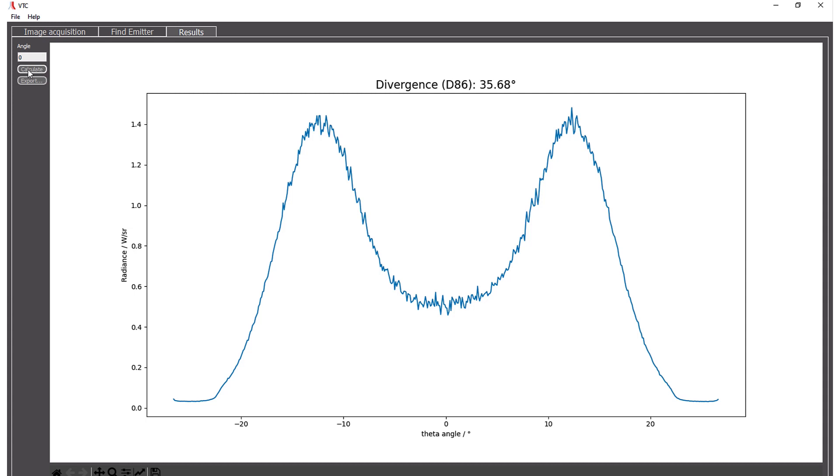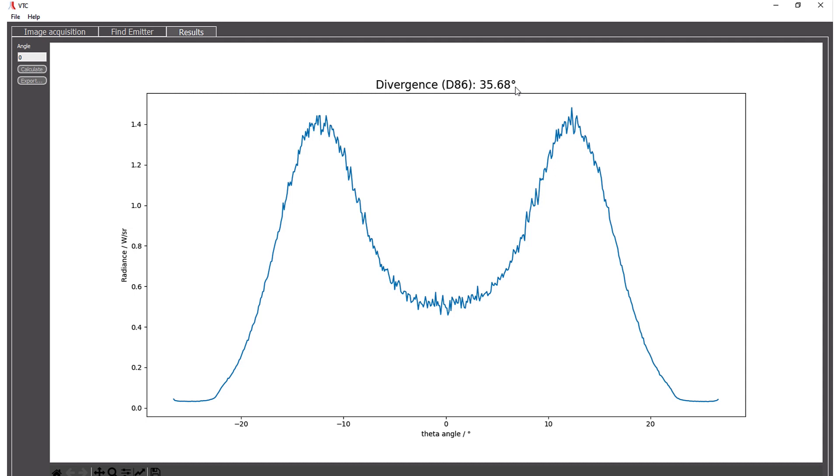Do the calculations and see this nice donut shaped profile. Where we have one maximum at minus 12 degrees. The second maximum is at 12 degrees. And the complete divergence calculated by the D86 method is 35.7 degrees.